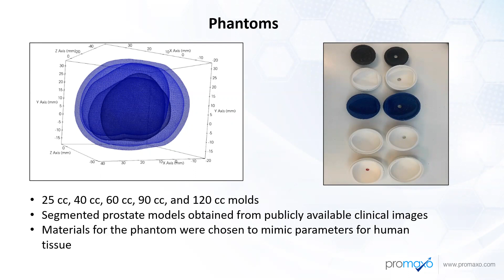First, a standard T2 scan of the phantom and fiducial markers was obtained on the low-field Promaxo MRI system. 3 or more needles were then inserted into each phantom, and the coordinates and depth were recorded. Next, a 1.5 Tesla T2 scan of the phantom was taken. The 1.5 Tesla was used as ground truth in the study. To obtain the ground truth coordinates, 2 urologists identified the needle track on the 1.5 Tesla image. In order to compare the planned target from the low field scan and the ground truth, the template was localized by 4 urologists, and the low field and the 1.5 Tesla scans were registered, or overlaid, to be in the same frame of reference. Registration was performed using the boundaries of the phantom box.